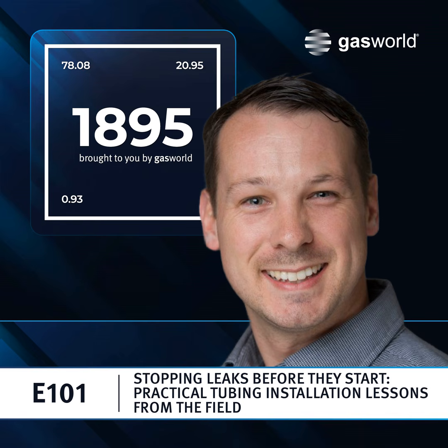So before you run the system, we use things like gap gauges. We can also do what we call kind of invasive inspection as well, where you actually open up the fitting, make sure that the ferrules are properly aligned and at the right location. And then certainly Swagelok fittings, I think most fittings have a remake ability to them as well. So you can remake those fittings for a significant amount of time to make sure that everything's good on the inside.